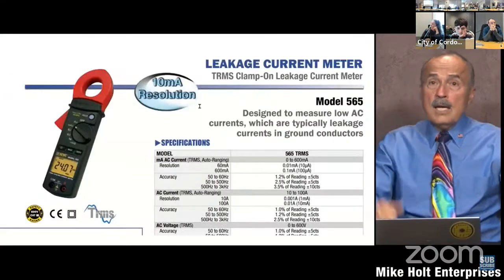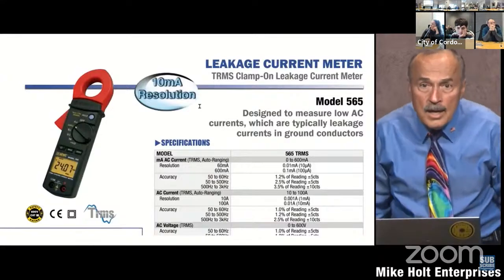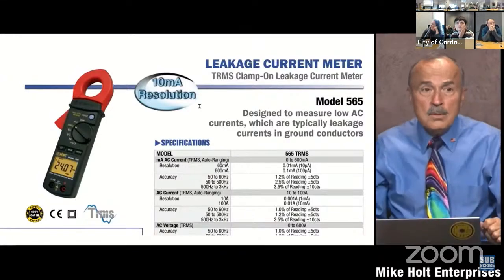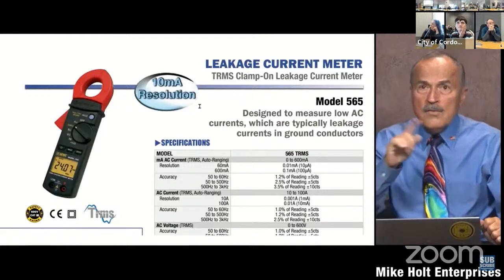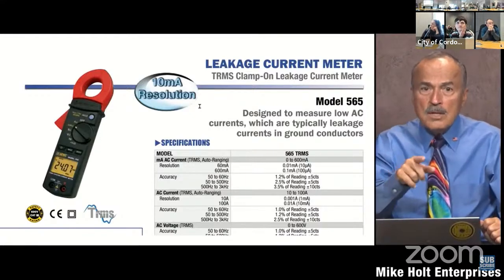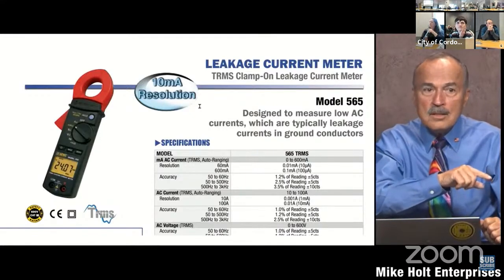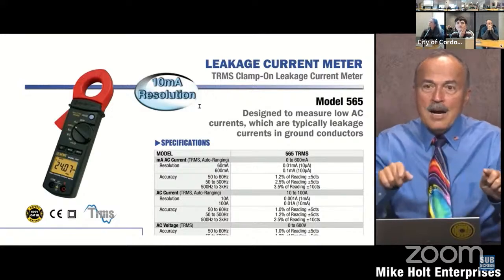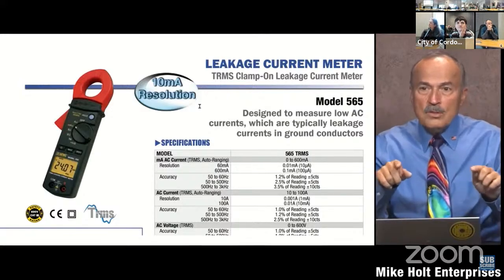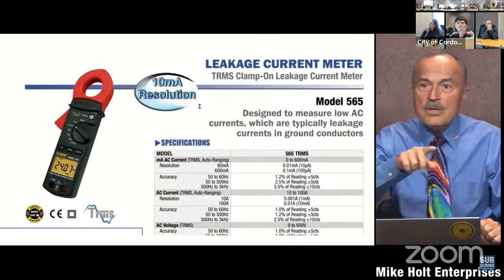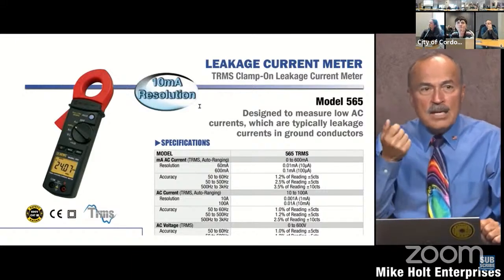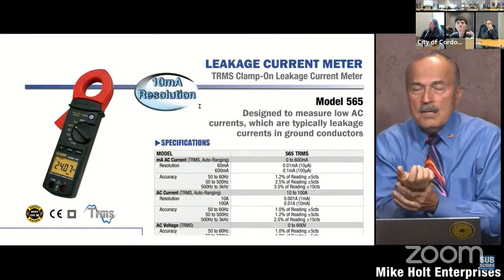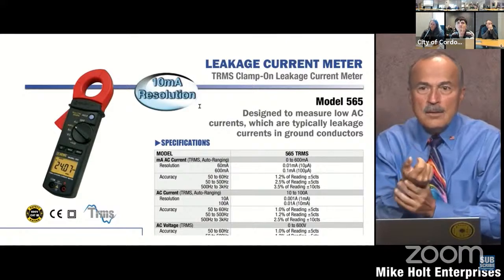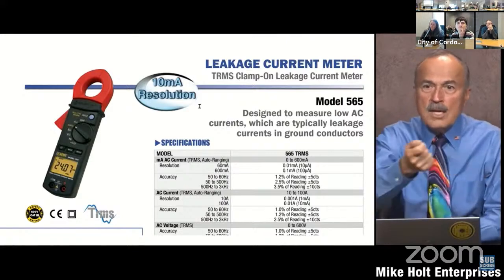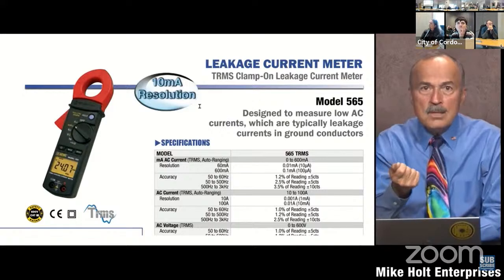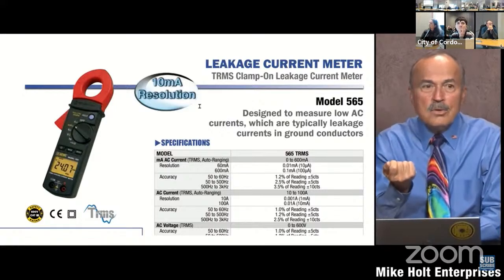The theory of this meter is like, wow, man, if the feeder dropped out, we've got to find out which of these guys is the problem. Well, none of them is the problem because none of them was more than 30 milliamperes. It's just that they all added up. Because if any one was more than 30 milliamperes, it would have taken out the 30 milliampere protection device. So having a leakage current detector, an ammeter set at a very low range, measuring these things, that none of them are more than 30 milliamperes becomes irrelevant. There's nothing you can do about that.